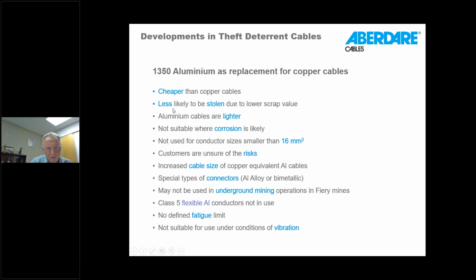So 1350 is not used for conductor sizes smaller than 16 square. We know that some customers are still unsure of the risks, and it's just a question of communicating and pointing out what installation requirements there are for these kind of cables to address that issue. The increased cable size of copper-equivalent aluminium cables can cause issues. Sometimes you have to increase the size of a replacement cable for copper up to 2 sizes larger, and that creates issues with bending radii when you want to install in switchgear and so on. So it can become an issue where you have tight spaces in which to install these cables.